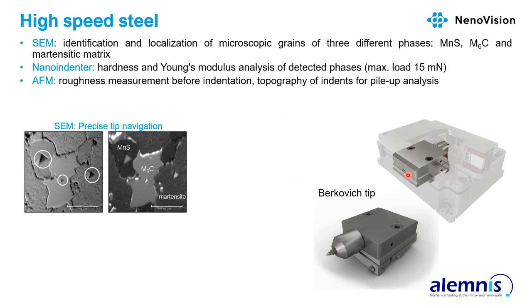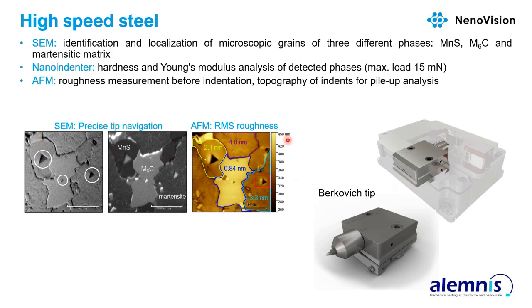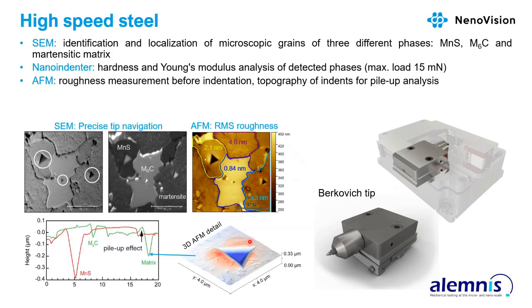So I have an example of high-speed steel. We can see in the SEM the nanoindents. The indents were made using the same force, but as there are different hardnesses of phases, there are different sizes of indents. So we measured the topography for roughness and later for the indent. We could see that there is some pile-up effect as we pushed inside the material, and we could measure the height profile. So we got the Young modulus, hardness, and the topography, what's going on.